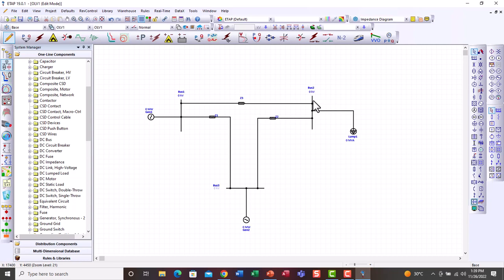Bus 2 is a load bus, also called PQ bus or PQ control bus. It has known variables P and Q — real power and reactive power — and the unknown parameters are voltage and shift angle. Bus 3 is a generator bus, also called the PV control bus, where the known variables are real power and voltage, and the unknown parameters are shift angle and reactive power.